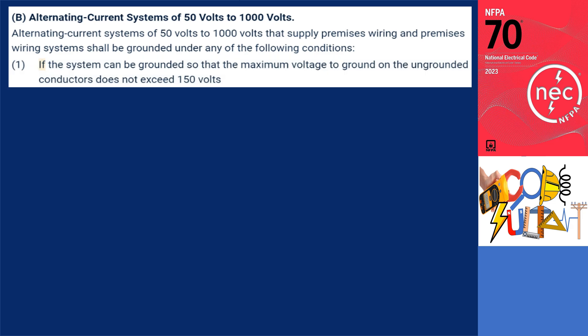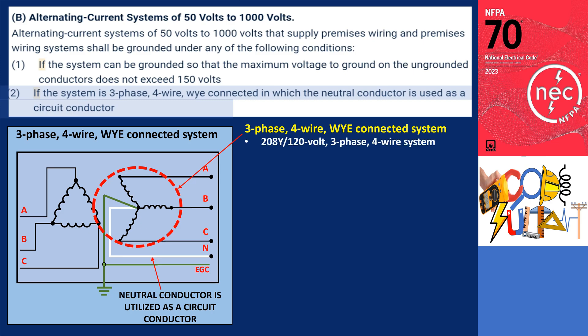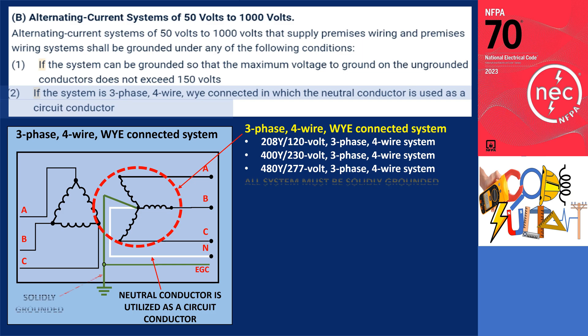For condition 2, if the system is three-phase, four-wire, Y-connected in which the neutral conductor is used as a circuit conductor. This condition is satisfied by common systems such as the 208Y/120-volt, three-phase, four-wire system; the 400Y/230-volt, three-phase, four-wire system; and the 480Y/277-volt, three-phase, four-wire system. In these systems, the neutral conductor is utilized as a circuit conductor, necessitating that all three-phase, four-wire, Y-connected systems operate with the neutral conductor solidly grounded.